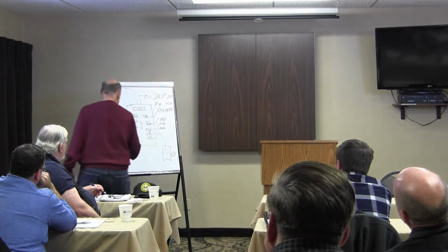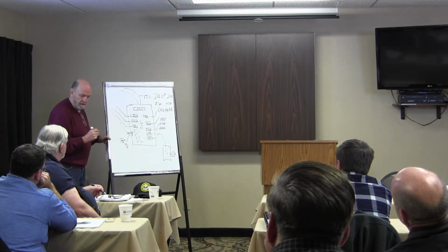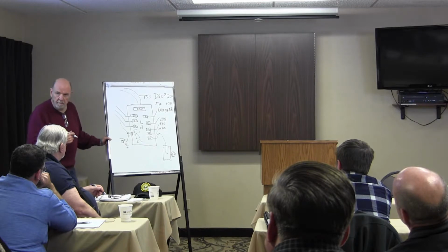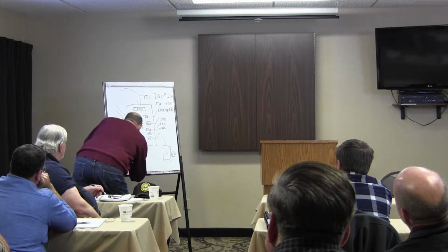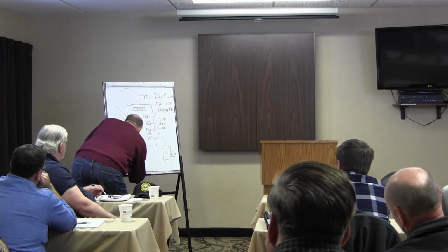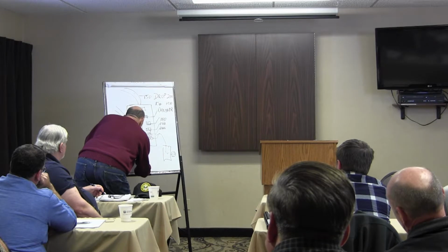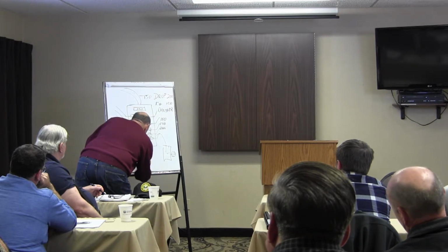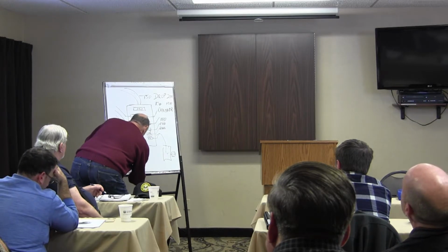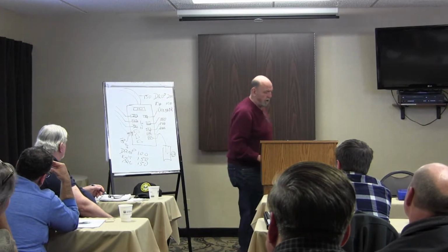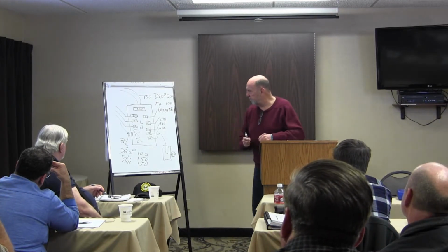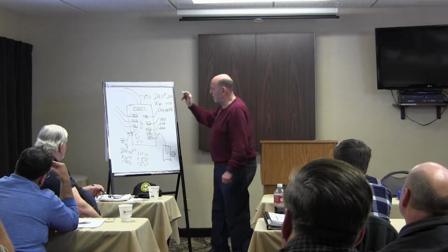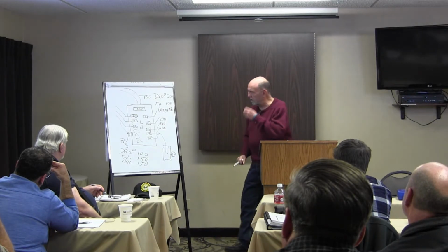Now, if I have a drop, an entrance, and a breaker, let's do some of this. I have a 100 amp drop, 150 amp entrance, and 150 amp main panel breaker. Service size, we've already determined, is 100, correct? Because this service drop is rated for 100.